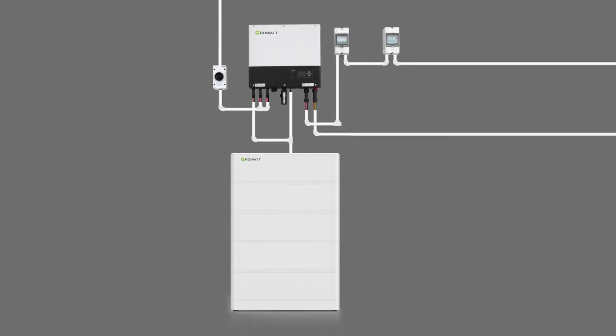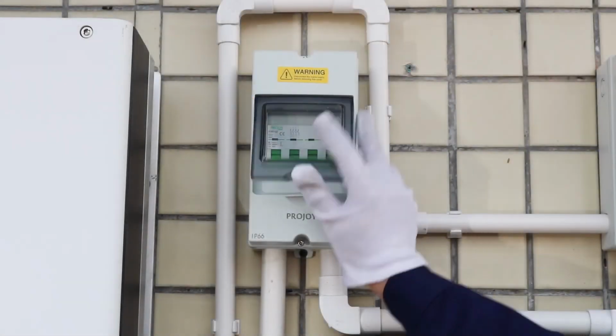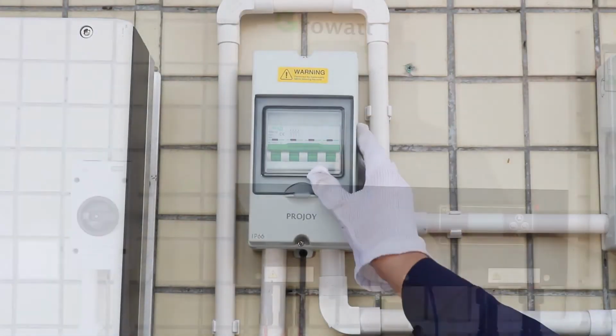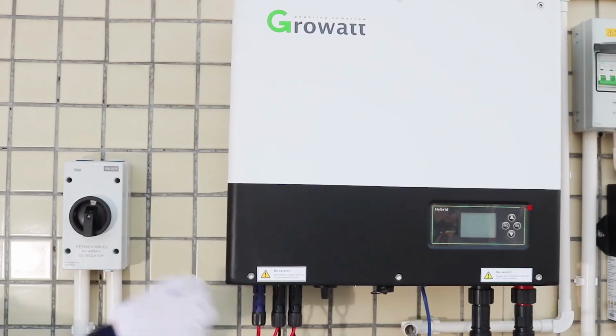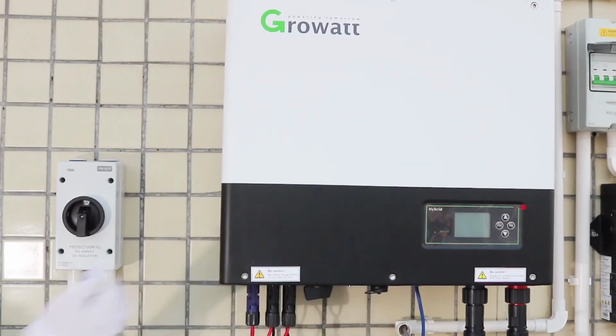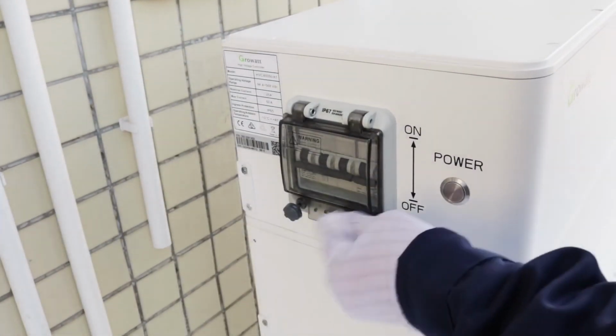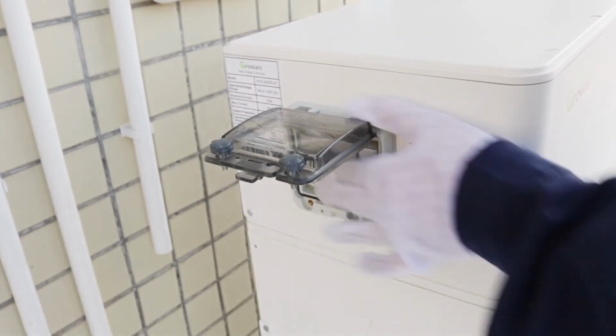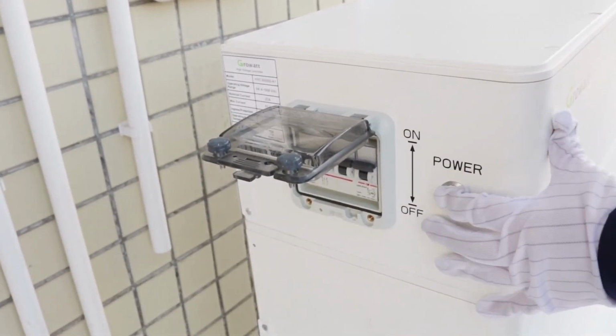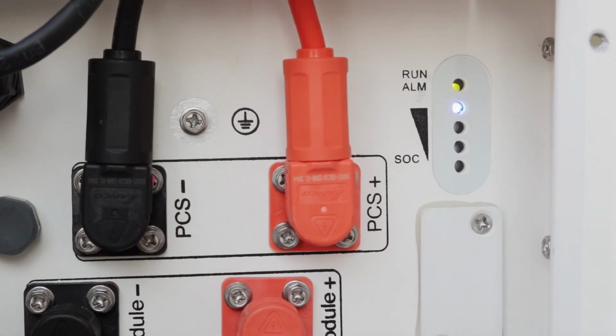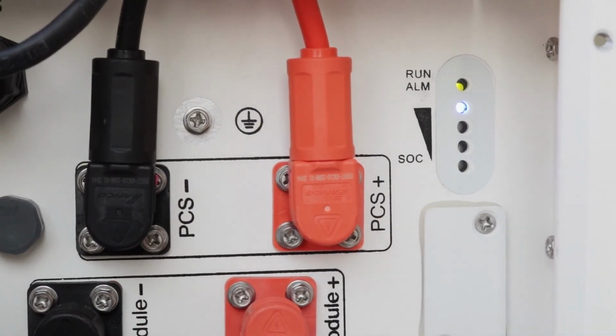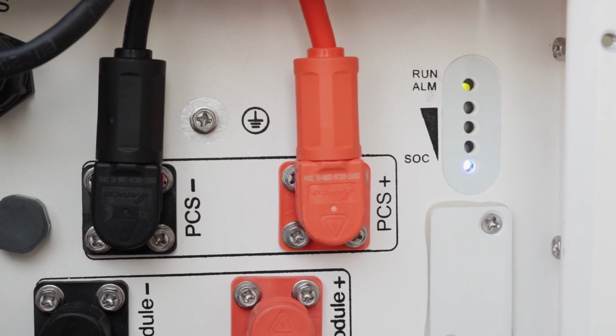As demonstrated, you can see the whole ESS system, and now we start to power up the whole system. Firstly, turn on the breaker between the grid and the inverter. Secondly, turn on the PV breaker and PV switch of the inverter. Finally, turn on the breaker of the BMS module and power on the battery system. Then the SOC indicator will flicker for a short time and finally stay always on.